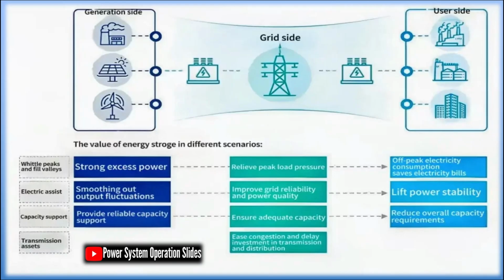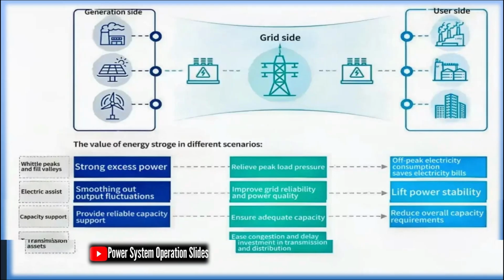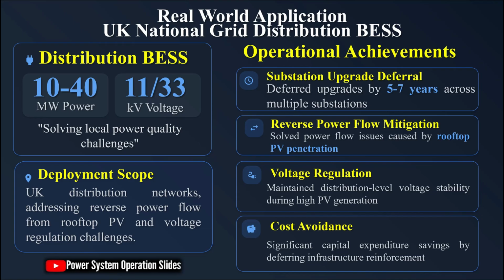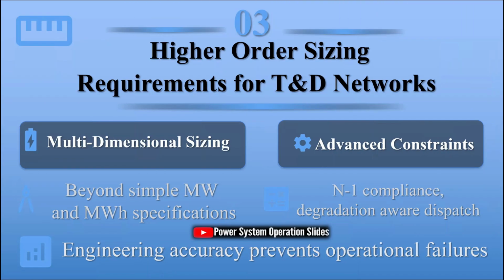These advanced constraints include N-1 contingency compliance, which requires that the BESS can provide required services even when one component is out of service, short-circuit contribution limits, which ensure that the BESS does not exceed the fault current rating of the connected network, harmonic distortion limits, which require that the BESS's power conversion systems do not introduce unacceptable harmonic content into the grid, degradation-aware dispatch, which optimizes BESS operation to minimize capacity fade over time, and seasonal load variation, which accounts for the fact that BESS requirements may vary significantly between summer and winter months.